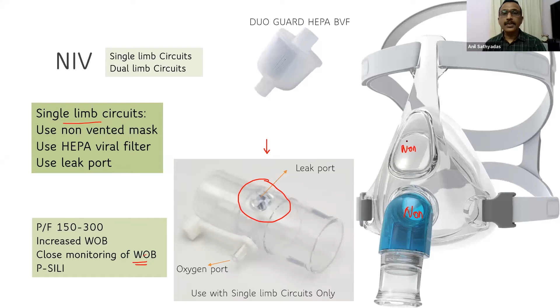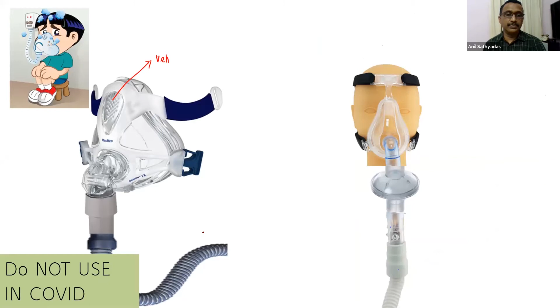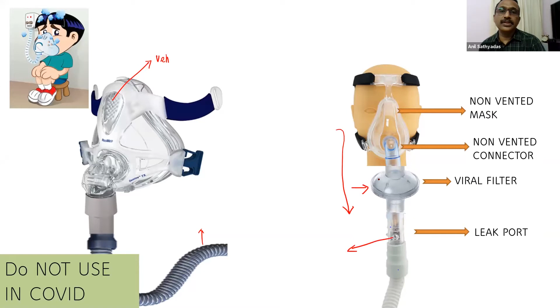So these are the modifications you should use. Don't use vented mask when you're using a single limb circuit. What modification you have to make is a non-vented mask, a non-vented connector, the bacterial and viral filter, and below that you have to keep the leak port. So this is how we should connect, so that any gas that is coming out from the patient is filtered by this viral filter and then only exhaled through the leak port. This modification you should make when you are using the single limb circuit.